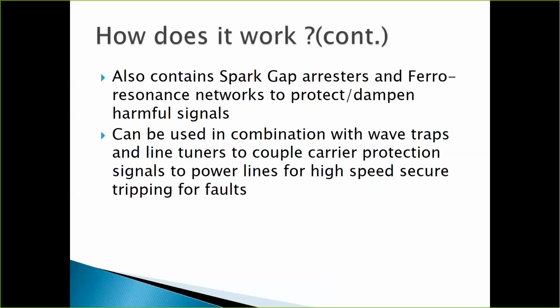Basically, you'll see that on any transmission line, you'll have some type of carrier protection, be it a directional comparison blocking or POTT or something such as that. So it's a really neat device. It's been around a long time. We have 3,000 more in service just in this service area. And they're relatively inexpensive, about $20,000 a piece as compared to a full inductive transformer type that you could see some places.